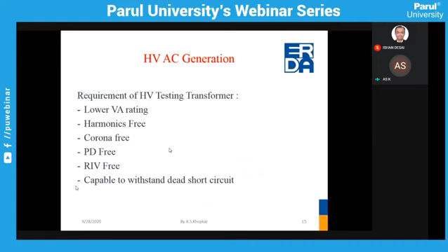And the last one, very important, is that it should be capable of withstanding dead short circuits. Normal transformers are not capable of withstanding such things. But in the laboratory, whatever transformer we use for high voltage testing should have withstand capability against a dead short circuit. Whenever we do the testing of high voltage products, there are only two possibilities: either the product will pass or the product fails. And if the product fails, it should not happen that the source transformer also fails. So whatever testing transformer we use, it should be capable of withstanding dead short circuits. Whenever a product fails, it converts into a dead short circuit.